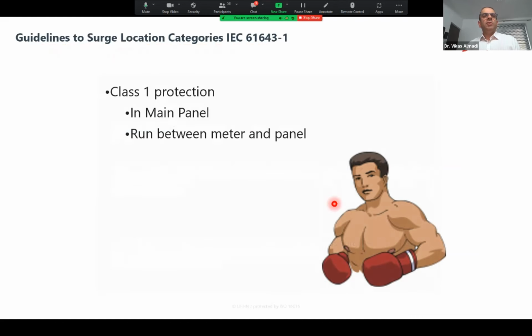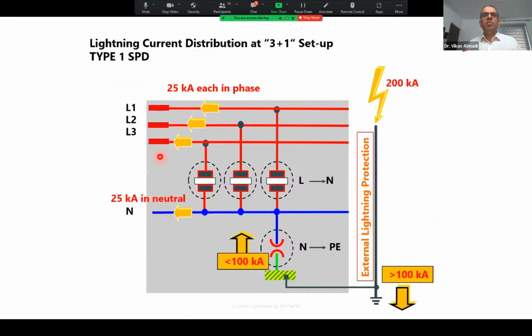Now talking about class 1 protection, it has to be at the entry level. Like your dust mat, you will put a major dust mat at the entry level of your home so that most of the dust is outside. So it is in the mains panel and it is protecting all the installation after the panel. It is not only for the meter or only for the panel, it is protecting everything behind the panel. Now the question is, is one sufficient for the building? In most cases it can be one, like small villa houses, one is sufficient.